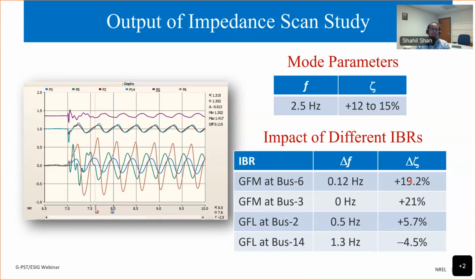Here we just show if we can really operate the system stably in steady state. Now, how it behaves during certain loss of generation, we also need to consider that aspect, just so that people don't think that I'm saying the grid forming capacity requirement can be reduced by just increasing the voltage control bandwidth, because transient stability and frequency stability are other metrics that we need to consider.